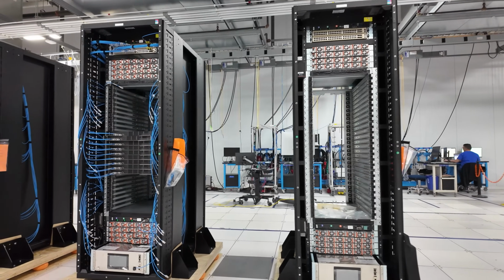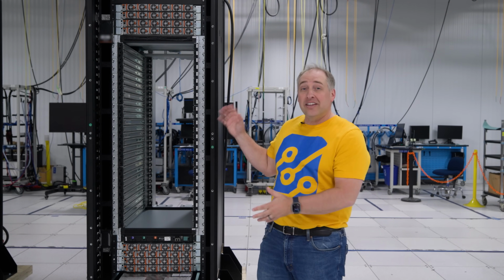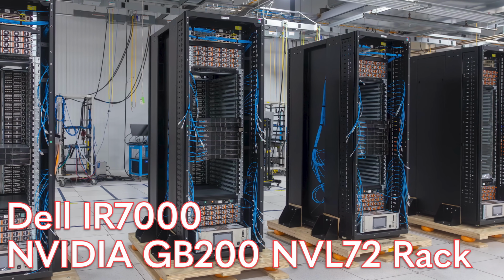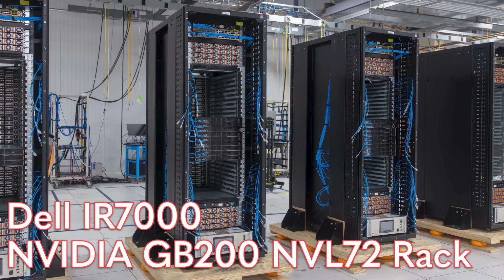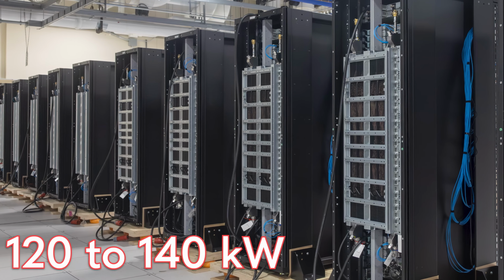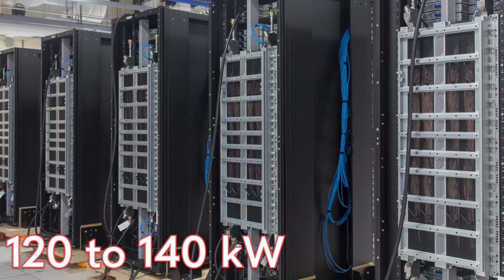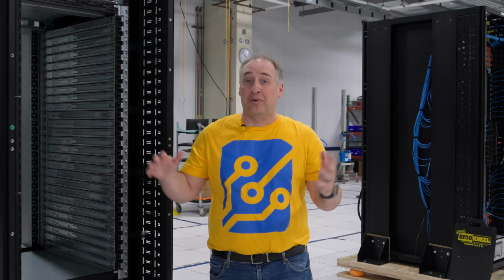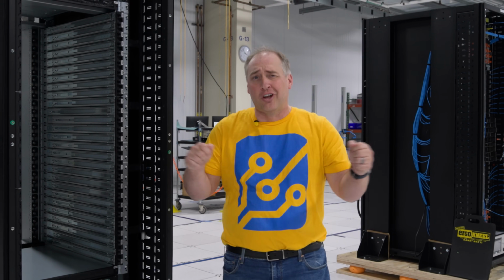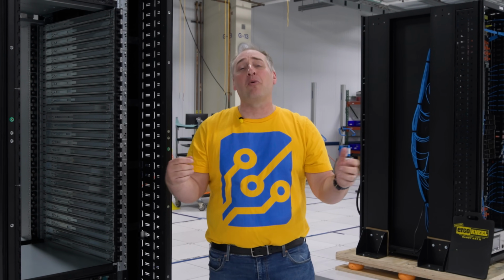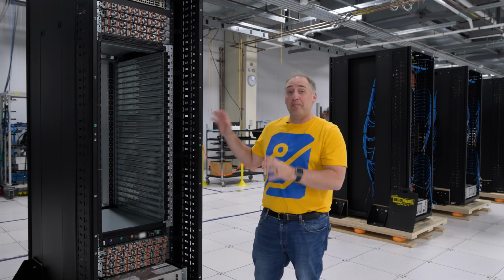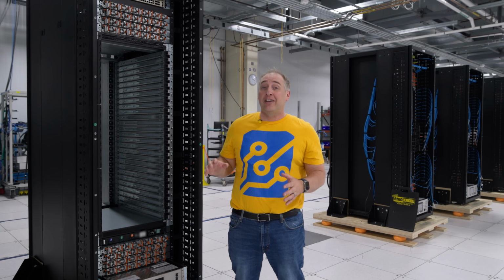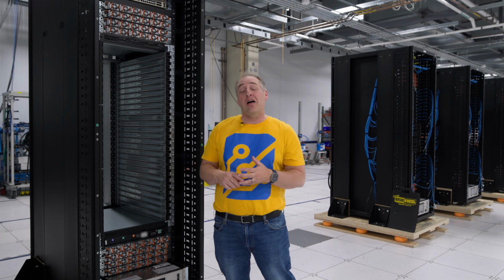Now, in generations past, power and cooling was always important, but not to the level that it is today. This is an NVIDIA GB200 NVL72 rack, which means that the power consumption is somewhere in that 120 to 140 kilowatt range. And so in those generations past where this type of work might have meant that you're just throwing a couple PDUs in and a couple rails in a rack, instead the power and cooling infrastructure in this has become a lot more complex and a lot more important.